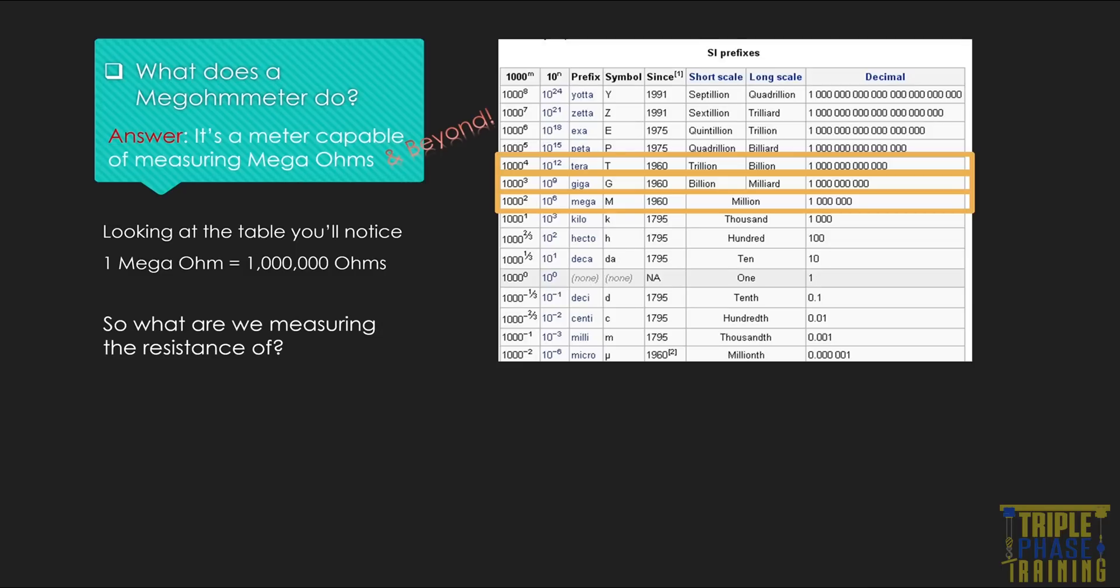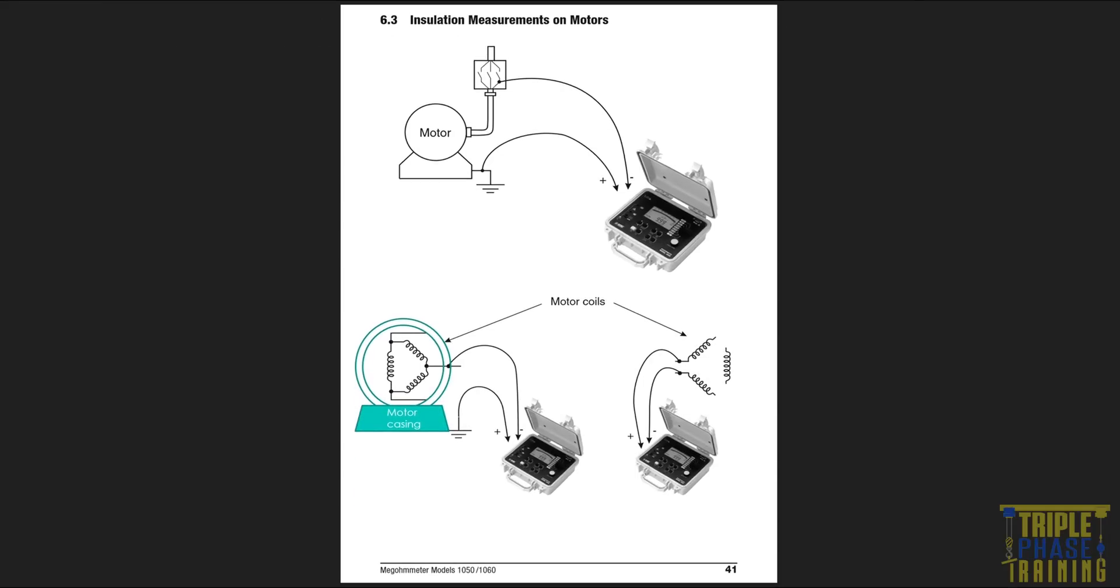So what are we measuring the resistance of? We are actually performing an insulation test. We are testing the motor's insulation, more specifically between the motor windings and the motor casing. If a fraction of current flows, it can be measured by the meter.